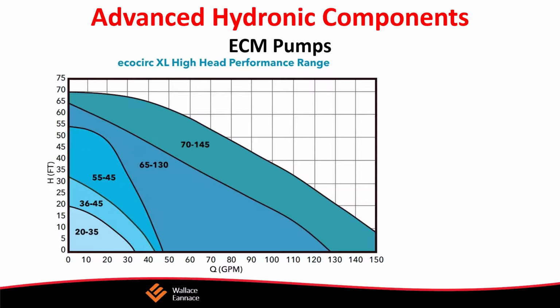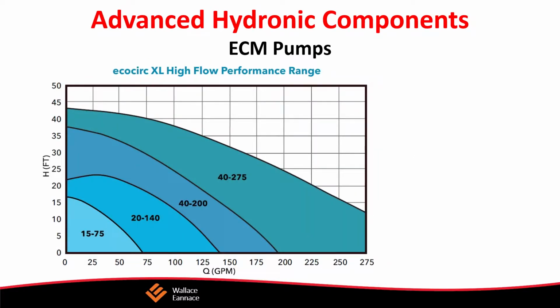The EcoCirc 2018 Plus also comes with Bluetooth capabilities, so you can actually communicate via Bluetooth. It can take a 0 to 10 volt input on all of our B&G pumps. They all put out a proportional signal. Once again, I said sometimes they'll have, say, a 10 to 1 turn down.